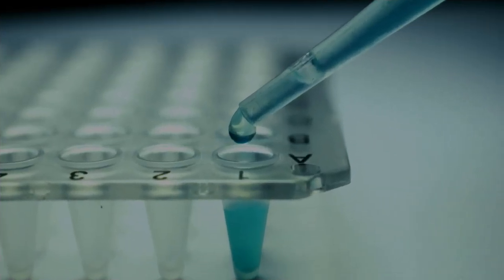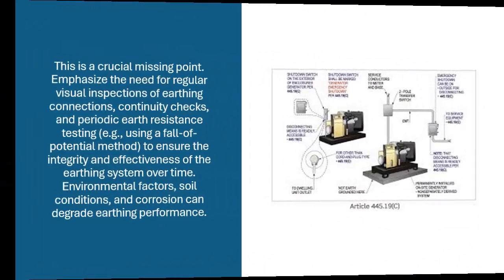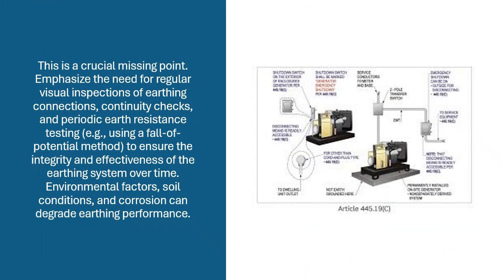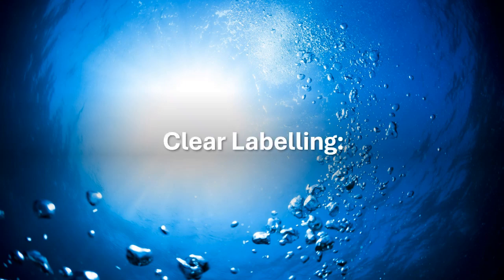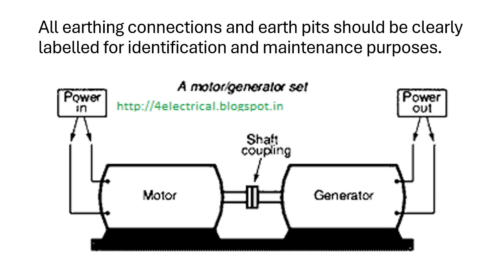Regular maintenance and testing. This is a crucial missing point. Emphasize the need for regular visual inspections of earthing connections, continuity checks, and periodic earth resistance testing, e.g., using a fall-of-potential method, to ensure the integrity and effectiveness of the earthing system over time. Environmental factors, soil conditions, and corrosion can degrade earthing performance. Clear labeling. All earthing connections and earth pits should be clearly labeled for identification and maintenance purposes.